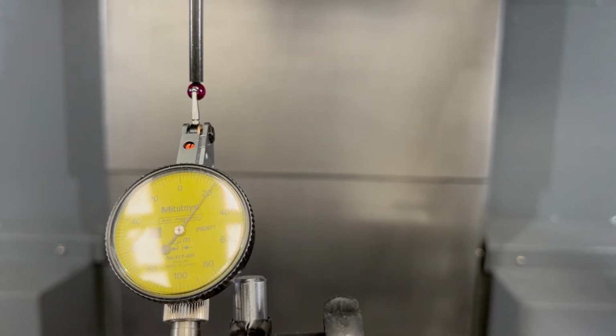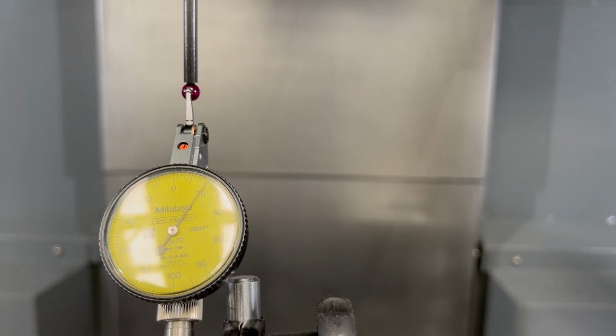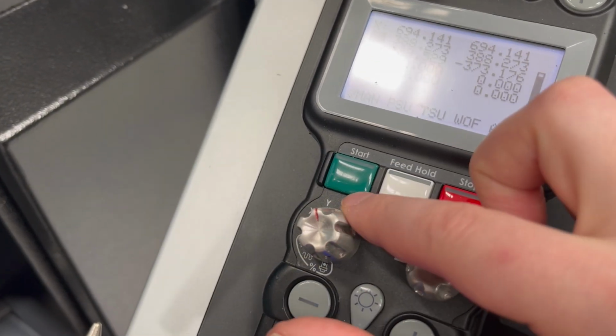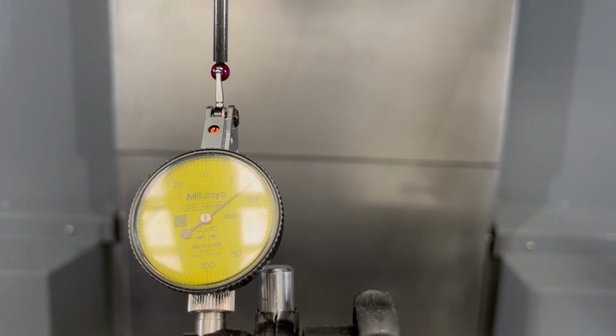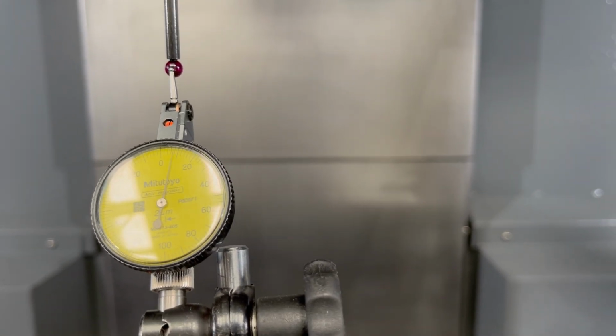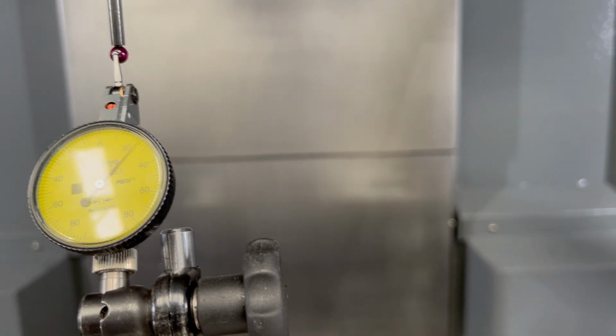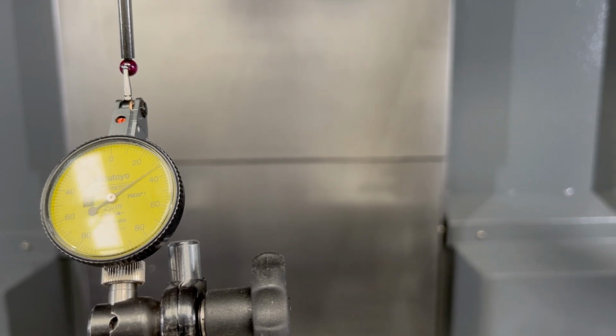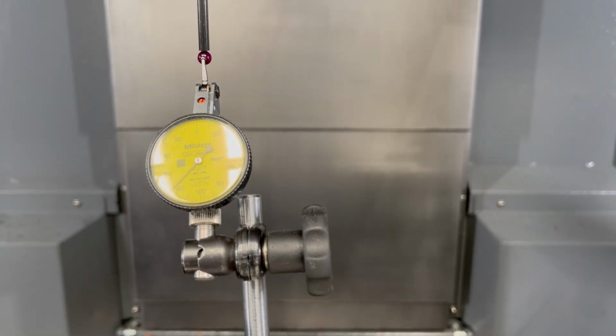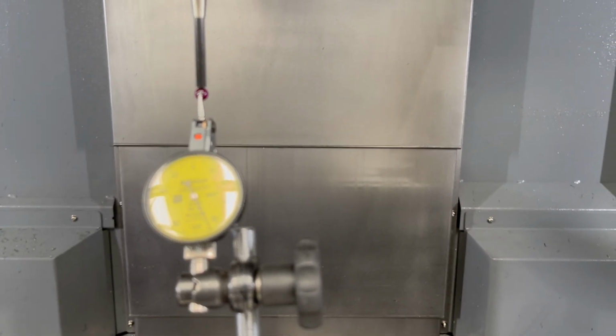But you want to clock this in as best you can, preferably so that when you spin that probe and the DTI is reading it, it just reads 0 all the way around. That would be the ideal scenario. The other thing to make sure of when you're clocking this probe is that I put my DTI on the center of that sphere, so on the center of the ruby. So put your DTI on there first, wind it incrementally up and down in the Z to find the high point, and then also do the same in the X. So wind it left to right until you find the high point.